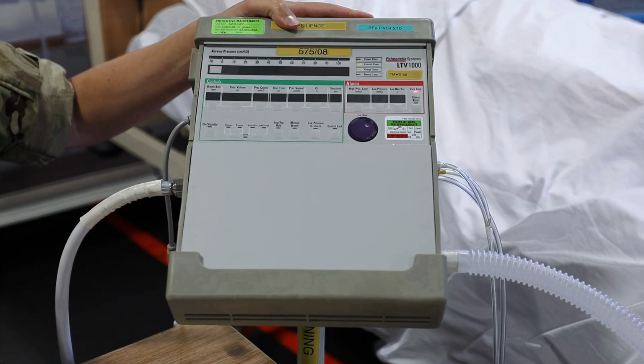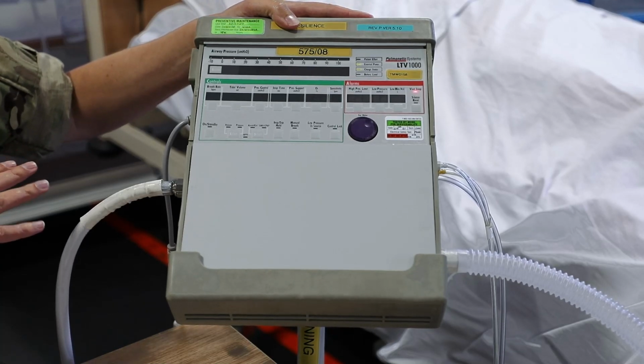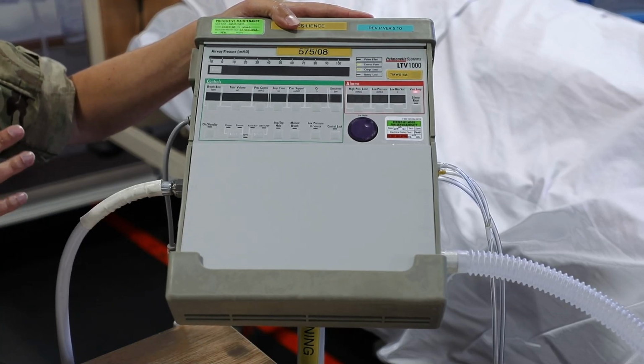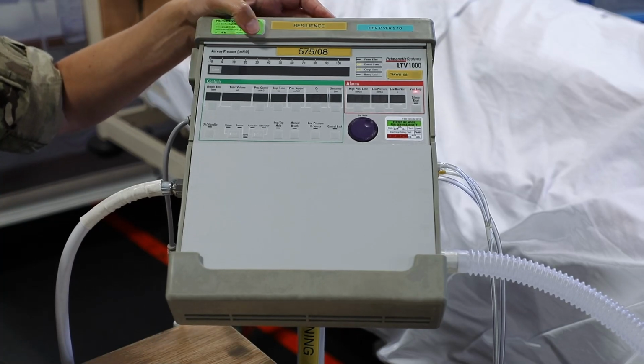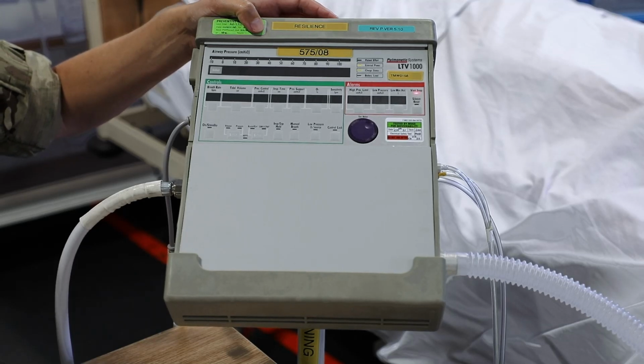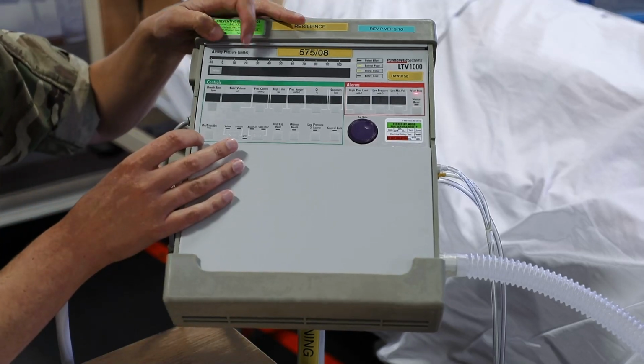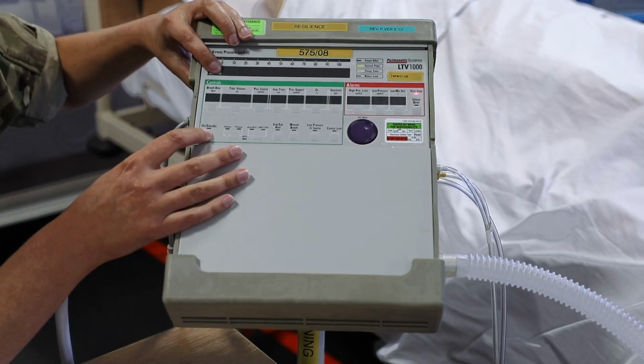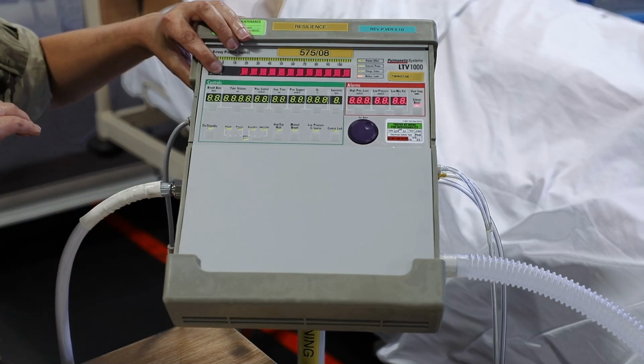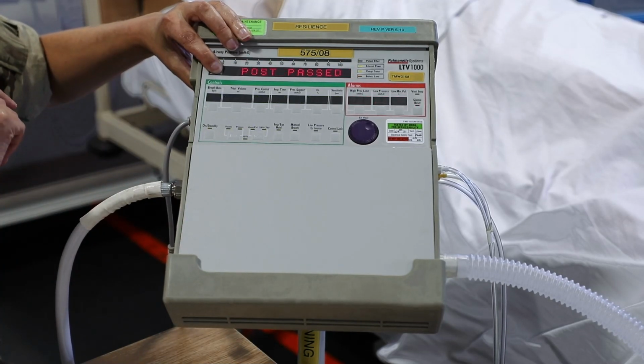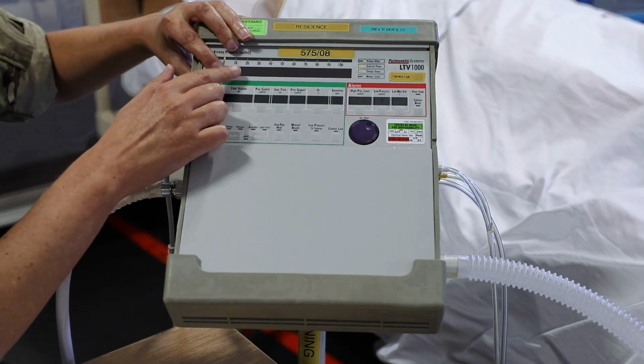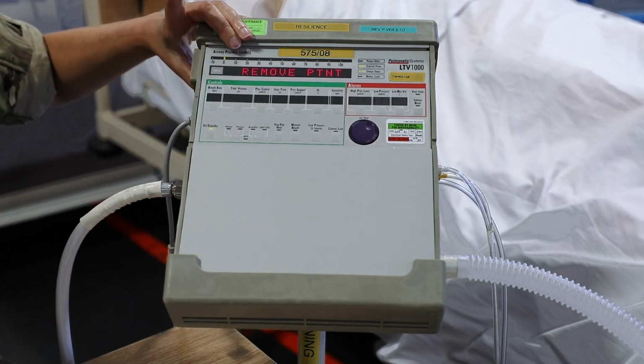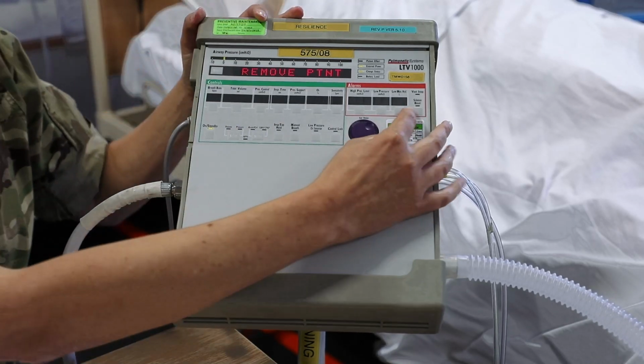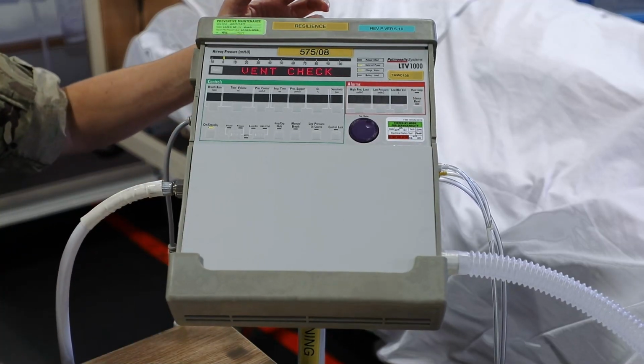You can perform this check plugged into the mains, so don't worry, you don't need to work off batteries at this point. So the first thing we're going to do is switch it on in its test mode, and to do that I'm going to press and hold the select button whilst switching it on, and I'm going to keep my finger on that select button until it confirms that the patient is removed, and you'll see that by the text on the display. So press and hold select and turn it on. Keeping my finger on that select button, it goes through a couple of checks and then it comes up with remove patient. You can now remove your finger from select and just press silence to take you into that vent check menu.